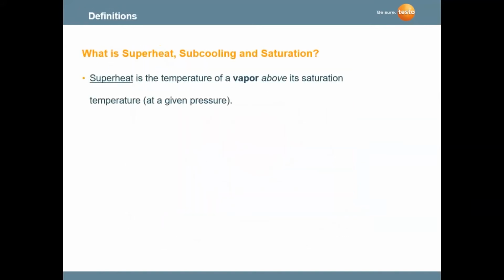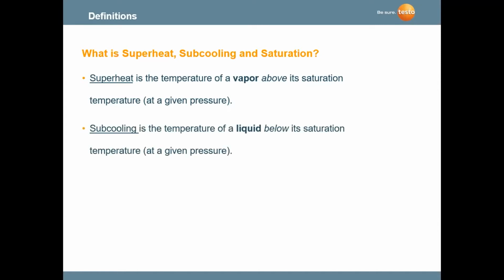So what is superheat, subcooling, and saturation? Superheat, as we showed on the graph previously, is the temperature of the vapor above the saturation temperature. Subcooling is the temperature of a liquid below the saturation temperature.